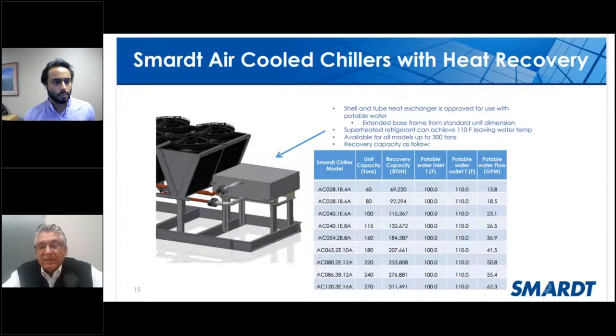Heat recovery is also a big asset with the air cooled product. It's a desuperheater that we've added to the machine, in series with the air cooled condenser. So you can get a 10 to 15 degree temperature rise that allows for preheating a boiler, preheating hot water, those kinds of things. Whenever the machine's running, you automatically get the heat rejected that would normally go straight to the condenser, through a desuperheater heat exchanger. And the controllability of that comes within the machine, along with all the valving and all the piping, and you see superheated refrigerant. Again, up to 110 degrees leaving water and up to 300 tons.